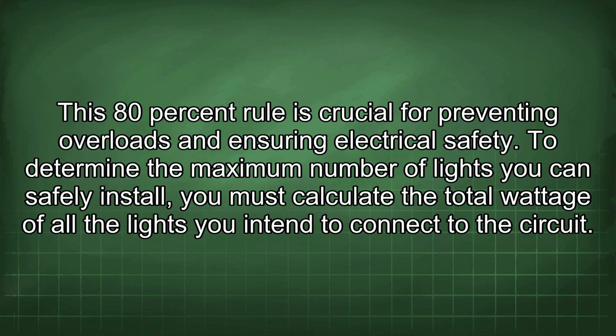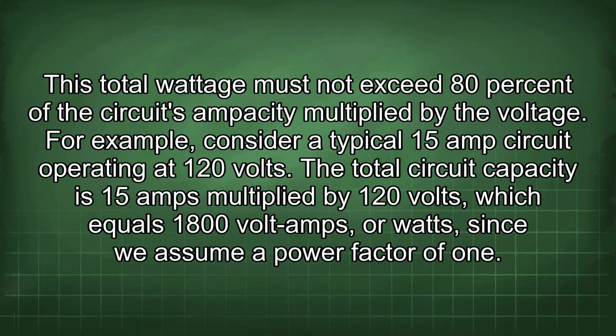To determine the maximum number of lights you can safely install, you must calculate the total wattage of all the lights you intend to connect to the circuit. This total wattage must not exceed 80% of the circuit's capacity multiplied by the voltage.